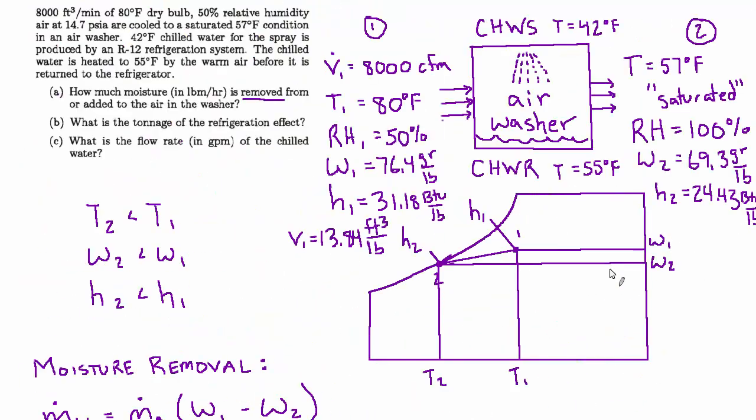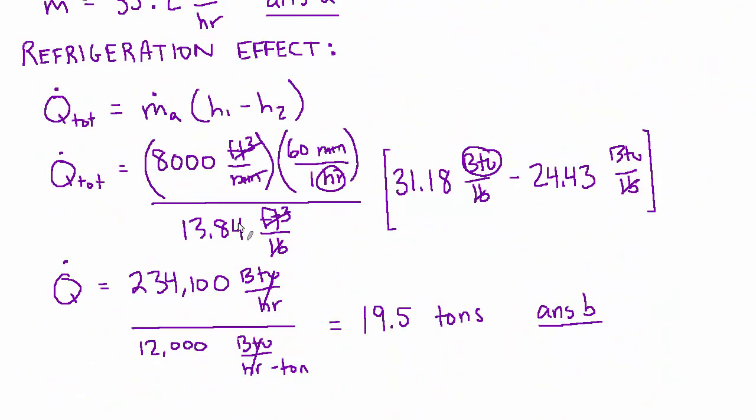And lastly, they wanted us to find the flow rate in GPM of the chilled water. So as this air is getting cooled, the water is heating up. It's being supplied at 42 and returned at 55. So there's this delta T of about 13 degrees. And we know how much energy has to be absorbed by the water. It's the same amount of energy that was removed from the air side has to be transferred into the water side. So what we just found that refrigeration effect in BTUs per hour or tons, however you prefer to think about it, that energy has to balance energy in equals energy out.